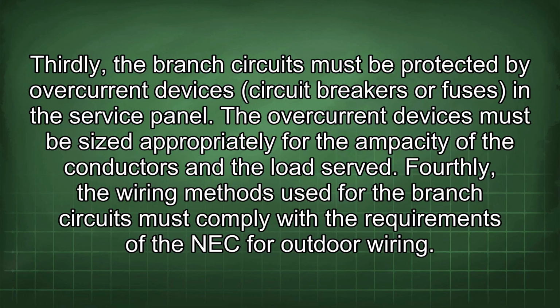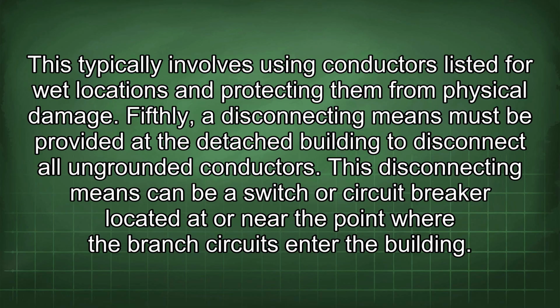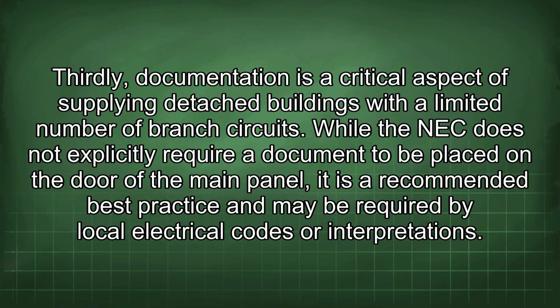Fourthly, the wiring methods used for the branch circuits must comply with the requirements of the NEC for outdoor wiring. This typically involves using conductors listed for wet locations and protecting them from physical damage. Fifthly, a disconnecting means must be provided at the detached building to disconnect all ungrounded conductors. This disconnecting means can be a switch or circuit breaker located at or near the point where the branch circuits enter the building. Thirdly, documentation is a critical aspect of supplying detached buildings with a limited number of branch circuits.